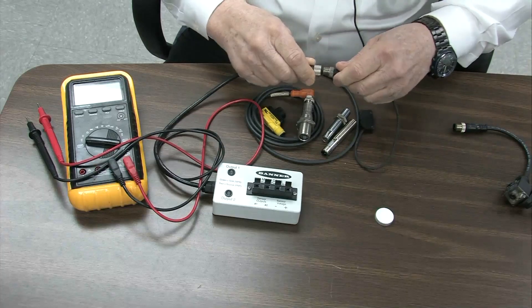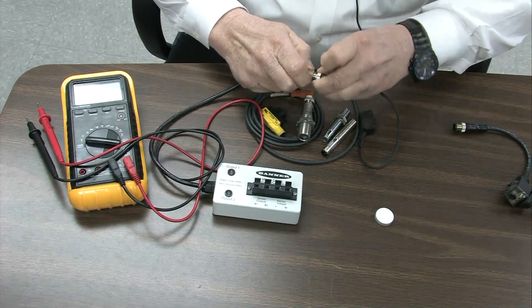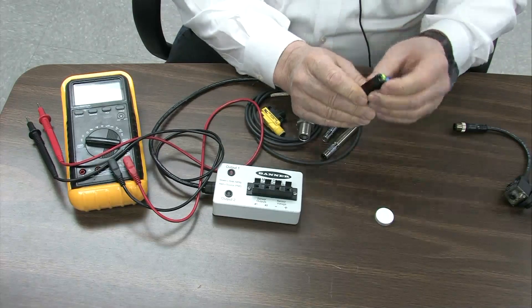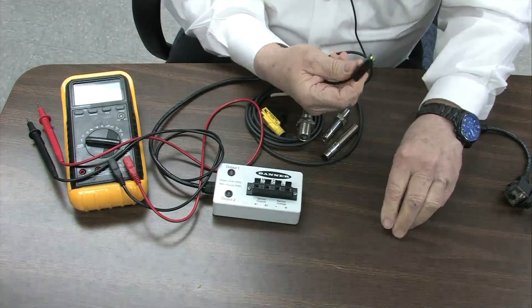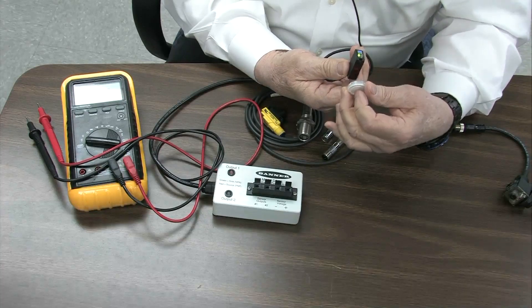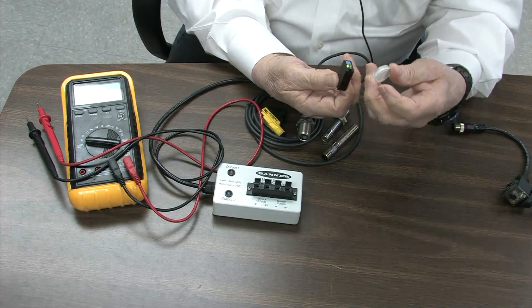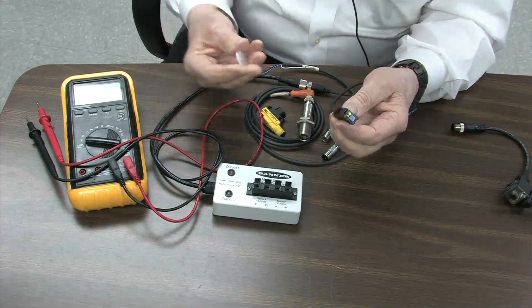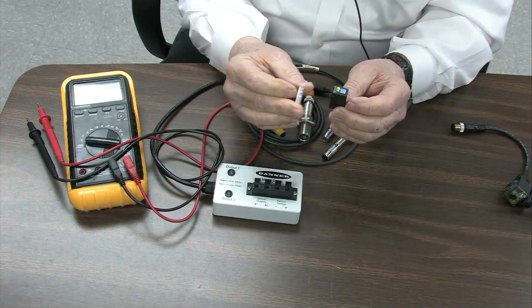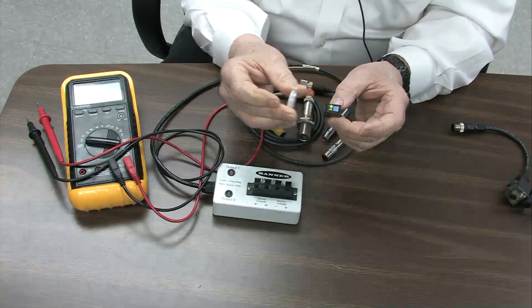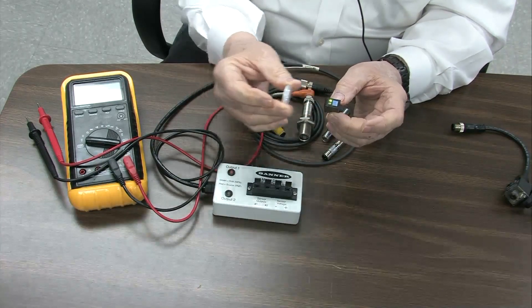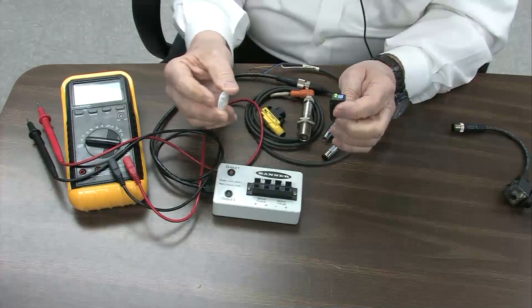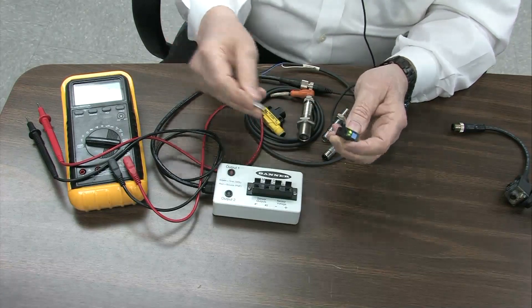This is a third device, different style. We have to be careful. We're not replacing parts by weight or by look and feel. So here's a photoelectric sensor. If I put the light up here in front of it, doesn't work. So I've got a green light in the front, says it's working. When I put my reflective device in front of it, I'm not seeing anything, not seeing an output on my device down here. So what does that tell me? It gives me a pretty good indication, even though I've got a green light here, there's something still wrong with this device. It needs to be replaced.